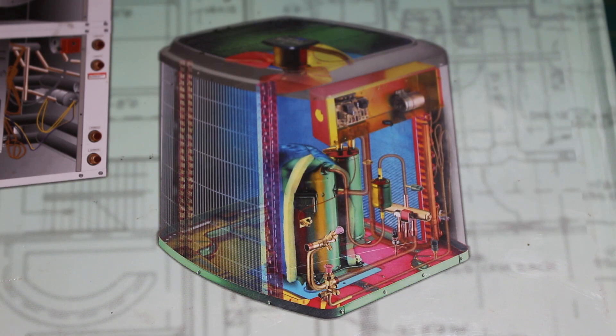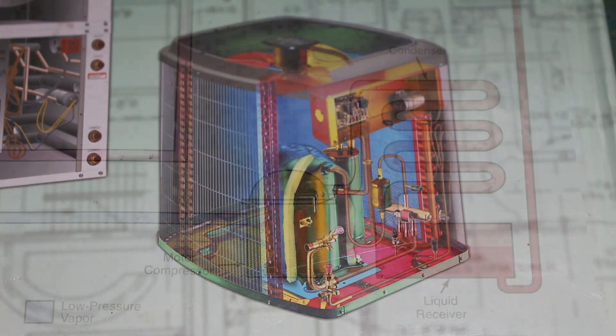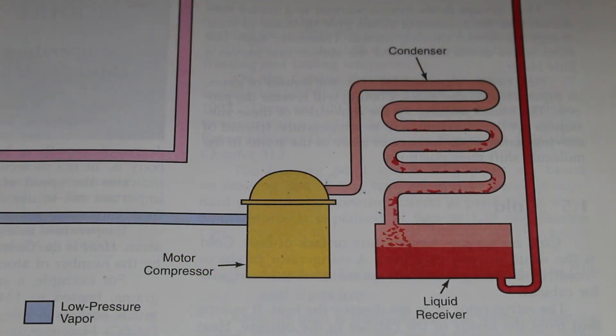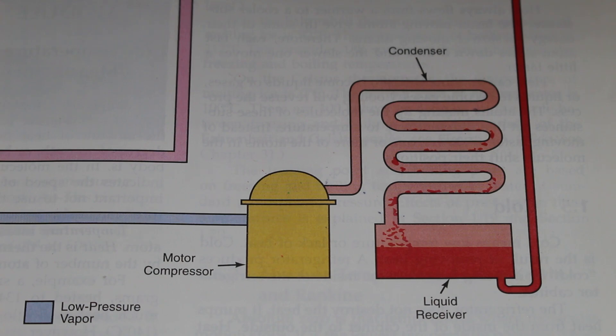Superheat can be found on the suction line and the discharge line as the temperature increases down each of those lines, either leaving the evaporator or leaving the compressor. When a manufacturer recommends a certain range of superheat, they are referring to the suction line superheat.